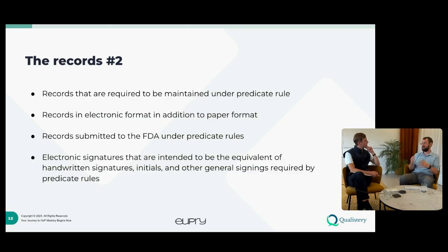It all gets a bit technical, so that's why I always go back to, if that stumbles your mind, then go back to: do I use this piece of documentation to make a GXP decision? Then yes, you would need to maintain it under 21 CFR Part 11. I hope that makes sense. There's always a lot of misconceptions regarding this. But again, going back to an educated guess would be yes, you would need to maintain it under 21 CFR Part 11. I definitely think we can easily dive into examples in the Q&A.